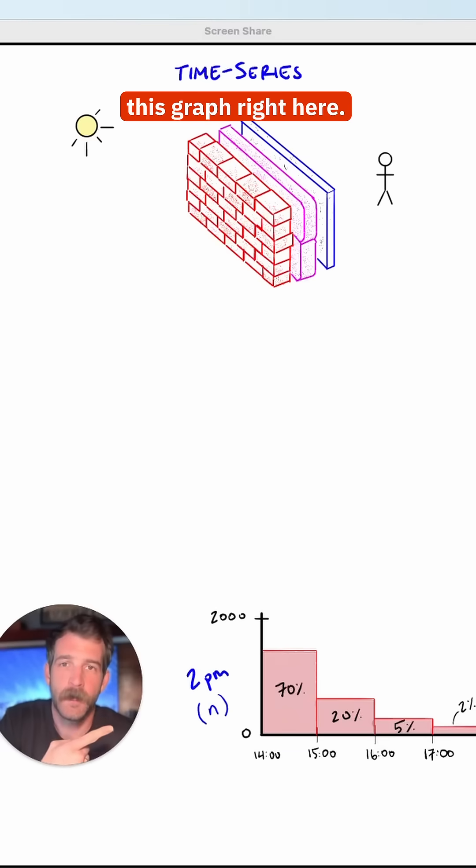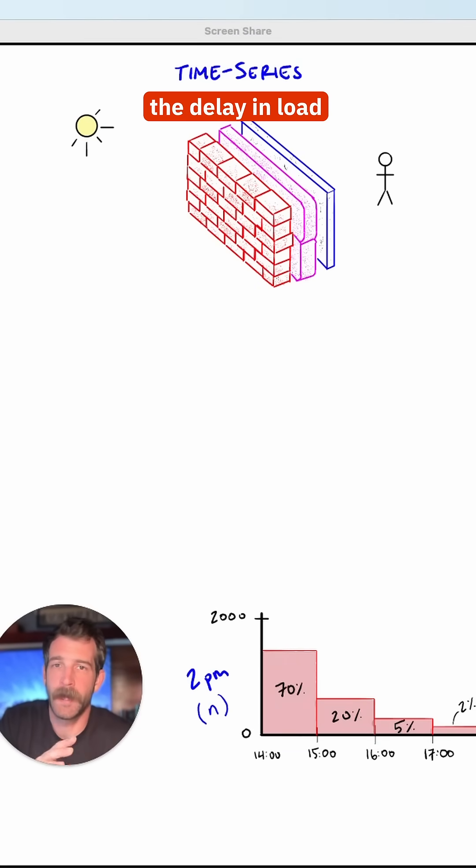This is where time series comes in. Take a look at this graph right here. This accounts for the delay in load entering the space. And the time series for an assembly defines how much heat is transferred with each passing hour.